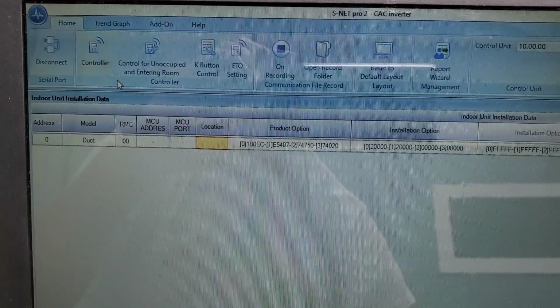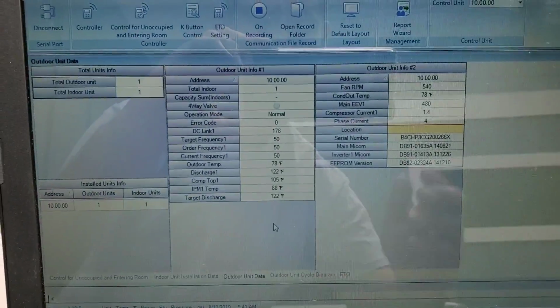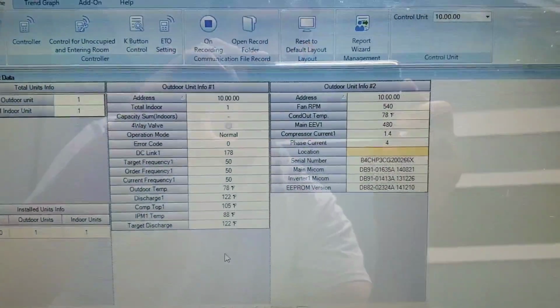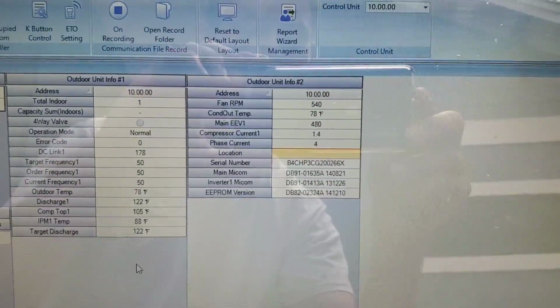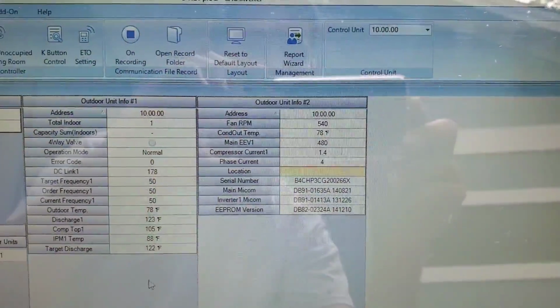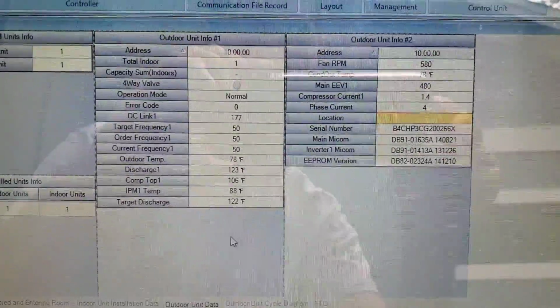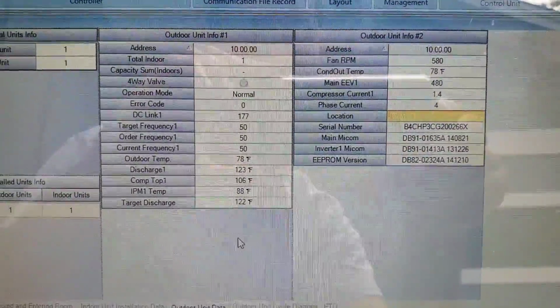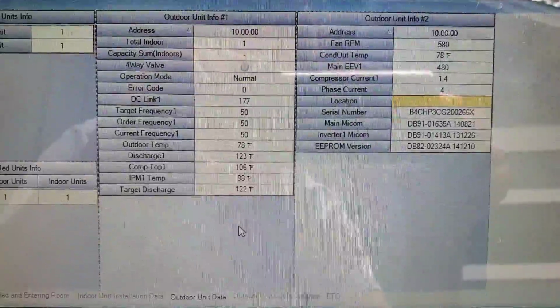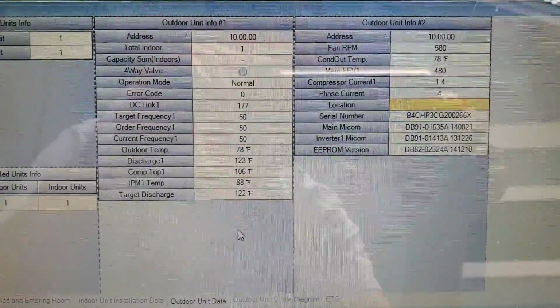Let's go back to home. Now I'm going to go down to outdoor unit. Sorry, this is a bit fuzzy guys, but it's hard to get this on. So, outdoor unit data, check it out. Right now the main EEV is at 480 steps, fan RPM at 540. My compressor current is 1.4. Outdoor unit temperature is 78, discharge 123, compressor top 106, target discharge temperature is 122.